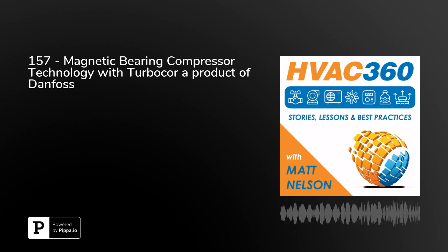It's capable of operating at a pressure ratio of 6.2, which is very good for water-to-water heat pump applications, and also good for some air-to-water heat pumps as well. Now, as far as the Turbocor goes, what kind of size range? When I think of heat pump, I get stuck into the smaller product range, but typically that's not where you see the Turbocor being applied. What sort of product range do you see out there?